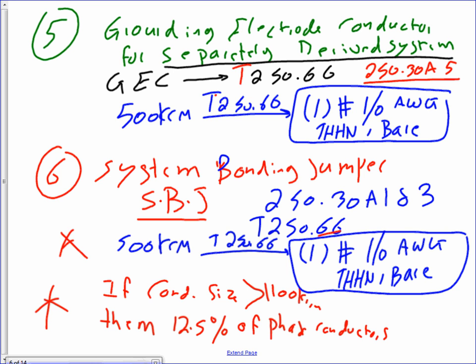I do have a note at the bottom that says if the conductor size is more than 1100 kcmil for the main bonding jumper, then you have to multiply by 12.5% of the phase conductors. Write yourself a note. We're going to do it in the next example. That's only if your conductor, which is the 500 kcmil, is more than 1100 kcmil. No. So this note at the bottom does not apply. It applies only if this conductor is more than 1100 kcmil. Is it? No. So it doesn't apply. All right?